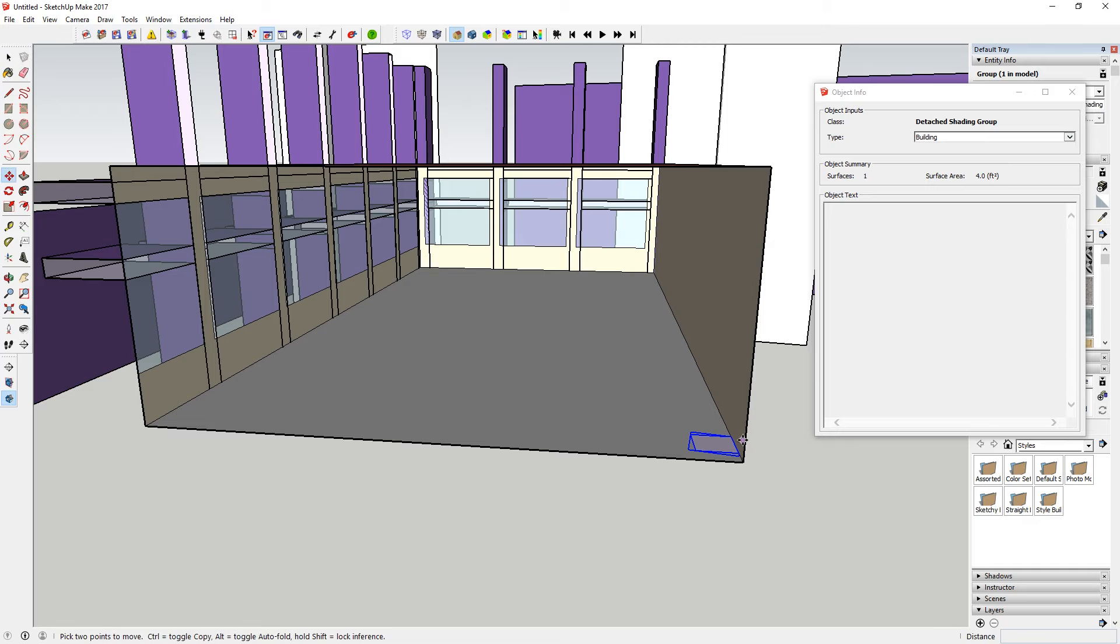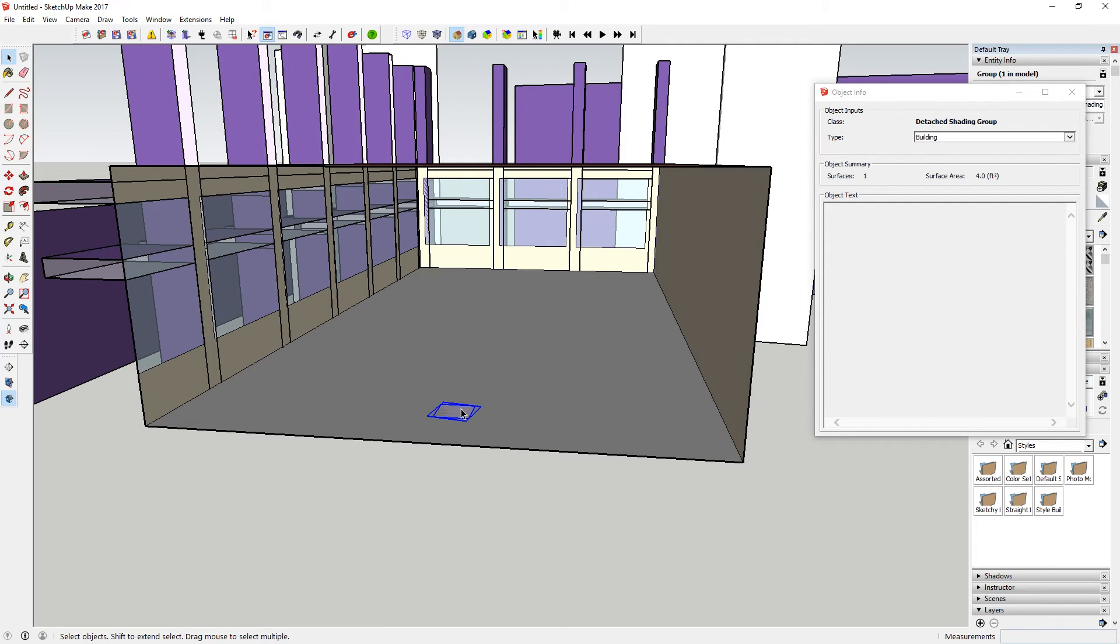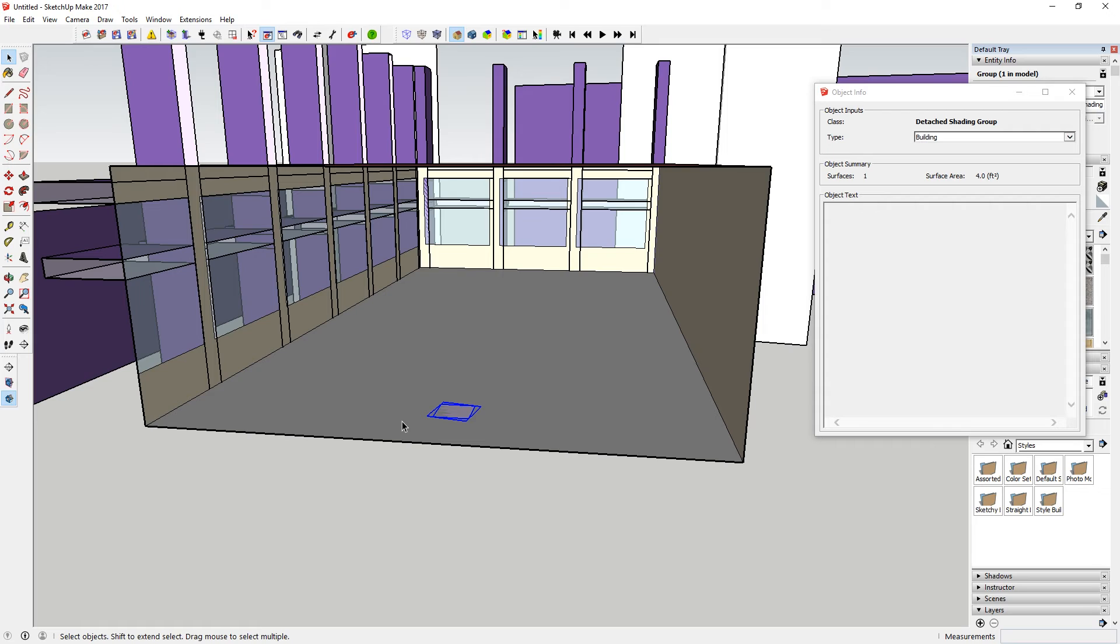But another strategy would be for me to say, well, I know I'm not going to get very much daylight back here. So perhaps I could get a more reasonable amount of light by moving this more towards the center of the room and now saying that only 50% of my lights are going to be controlled by the sensor. So from this point towards the glazing is going to be controlled by the sensor. From this point to the wall would not be controlled by the sensor, meaning these would be on according to the schedule and further limited by the amount of daylight that's available.